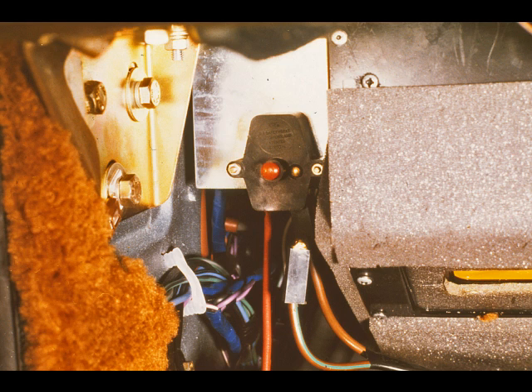Now disconnect the thermal circuit breaker output and measure the voltage at the terminal. If the reading is 0, depress the reset button. If the reading remains low or 0, the circuit breaker is faulty and must be replaced. If, however, the voltage is correct, reconnect the output lead, then recheck the voltage. If it has dropped to 0, the circuit breaker has tripped, probably due to a short circuit. This must be found and rectified.